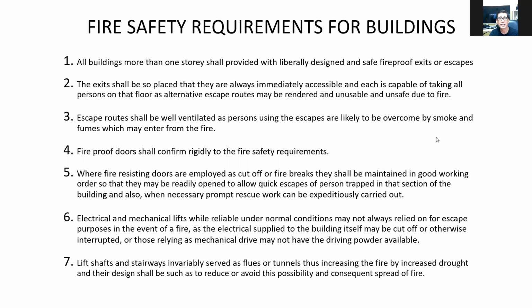Where fire-resisting doors are employed as cut-off or fire breaks, they shall be maintained in good working order so that they may be readily opened to allow quick escape of persons trapped in and out of the building, and also when necessary, prompt rescue work can be expeditiously carried out. Okay, so you need to maintain the fire exit doors. No? You need to make sure that the locks are operable, that the hinges are in place, that the face of the door is not damaged. So those are some of the points that you should observe in the inspection of a fire exit door.